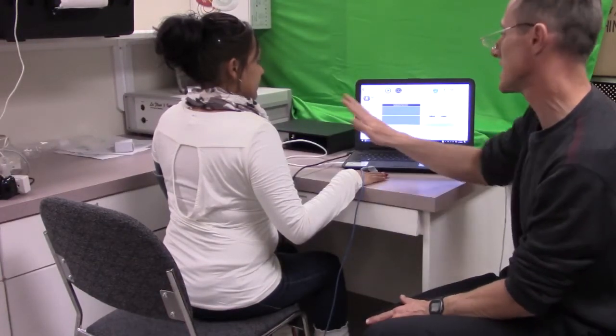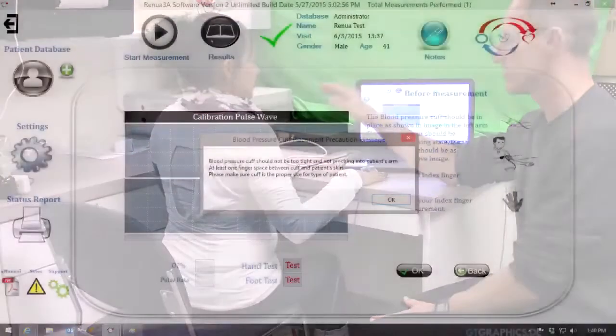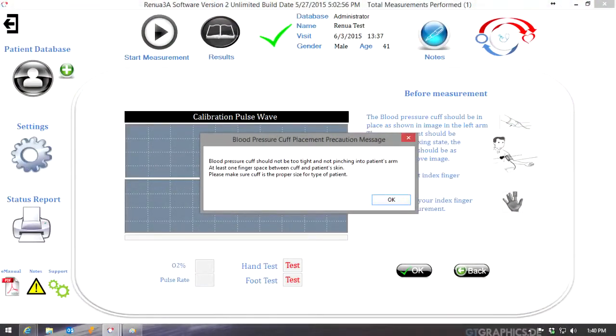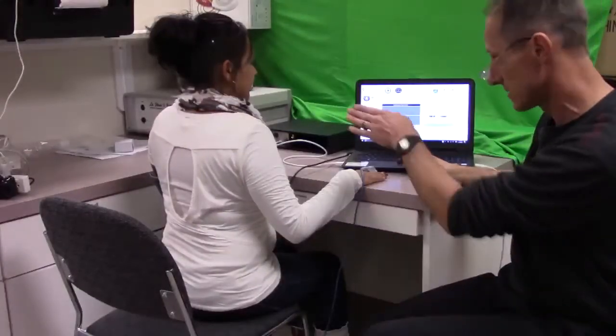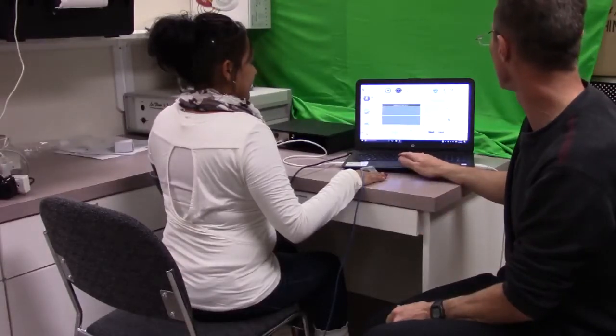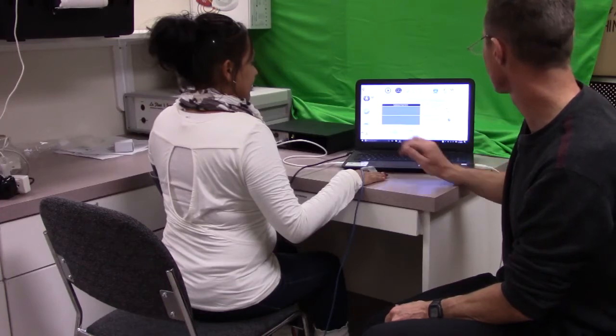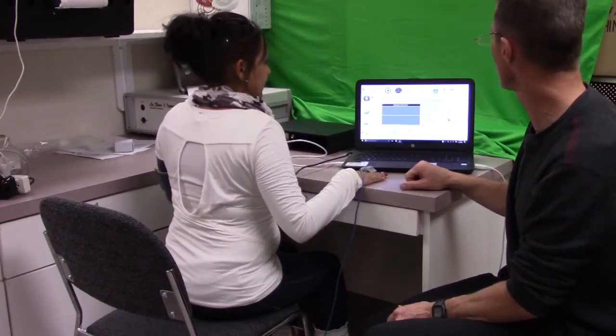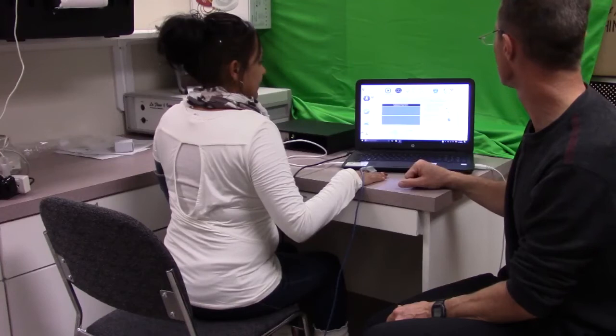So here it's asking me, is the blood pressure cuff on, which it is, and the pulse oximeter is on. I'm going to go ahead and hit start, and I'm going to get that blood pressure value. As that is getting that blood pressure value, I'm going to hit OK, and then the test will begin. So we just sit here quietly. The test will start. Phase 1.